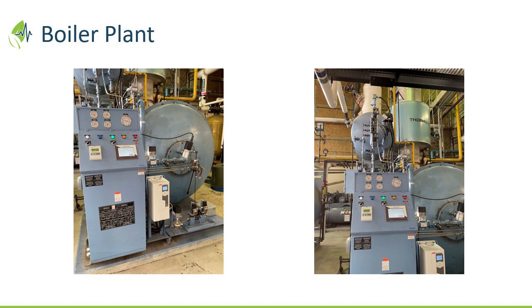So when you say condensing, that's not pure water, right? That's nasty stuff. Well, it's slightly acidic. It is, yeah. It's not pure water, but it is slightly acidic because it's from the byproducts of combustion, so it can corrode if it's not all stainless steel, but it's also just hanging around in there. It can cause a number of problems. So, and it would just drain right down into the boilers? No, in Brent's instance, he's pretty safe because there's a T there, but it'll all pool at the base of the stack if it occurs, so that's not great.